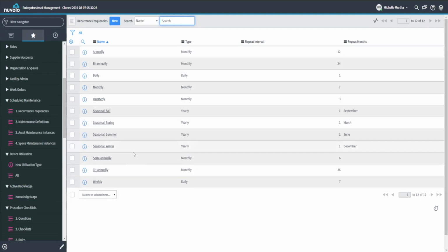I've also seen this used where we'll set up a schedule where I want it done monthly, except when we're doing the annual, like the annual will also include the monthly work. So we set up one schedule that does 11 months, and then that 12th month is the annual one. So you'll see stuff like monthly except September, for example.